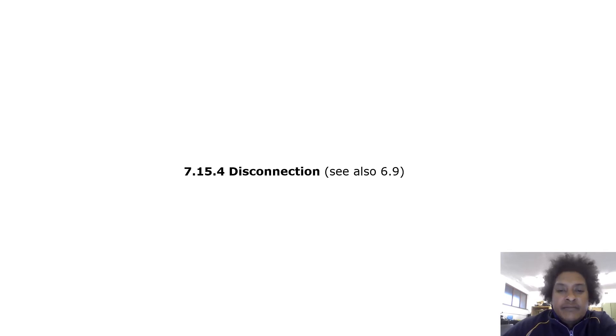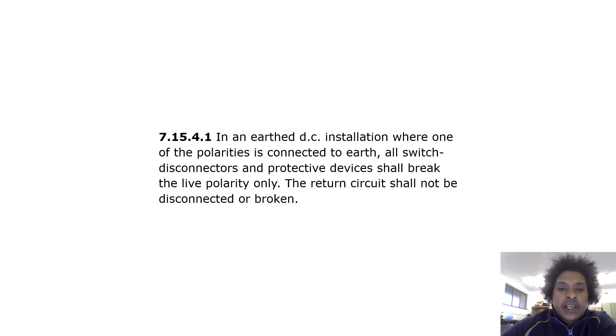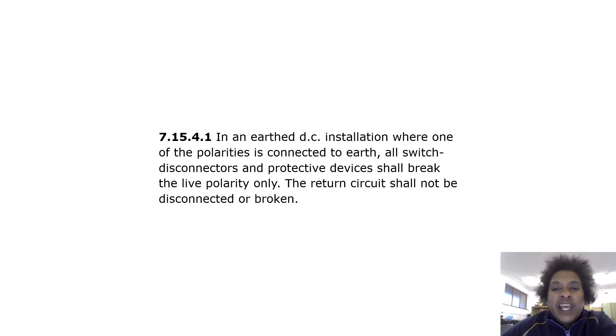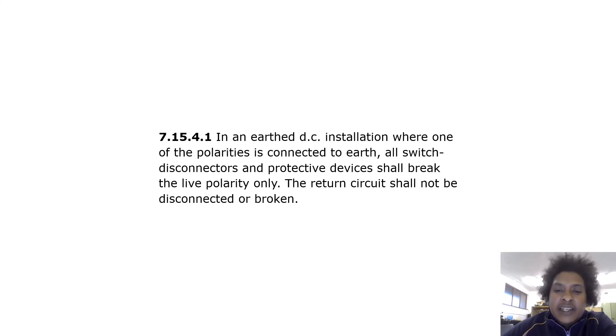Disconnection: in an earthed DC installation where one of the polarities is connected to earth, all switch disconnectors and protective devices shall break the live polarity only. The return circuit shall not be disconnected or broken.